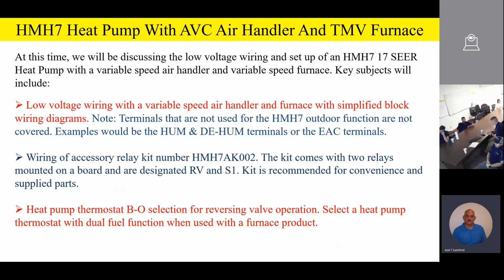So this is a simplified block wiring diagram. So there's some terminals on the variable speed unit that we're not going to talk about, only because it has nothing to do with the outdoor function, and just to keep the block diagrams nice and simple to look at. Now, please remember, team, on the variable speed products, it doesn't matter if it's a variable speed air handler or if it's a variable speed furnace, you're going to have to use that 002 kit, that 002 relay kit, because it has 2 relays on it. And those relays, we're going to be using both of them. So make sure that you have the 002 kit for the variable speed product. And again, we recommend these kits for convenience and all the supplied parts in there.